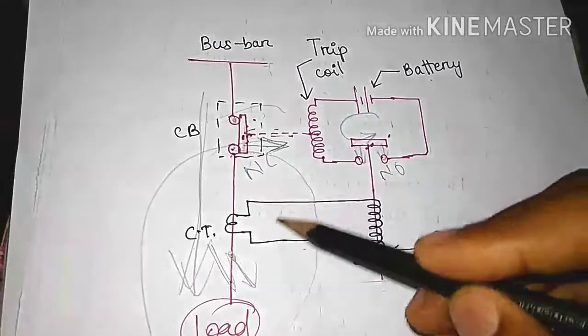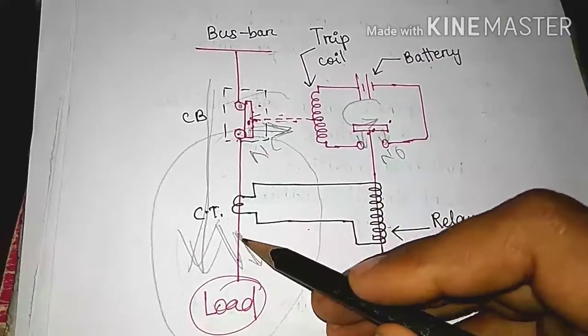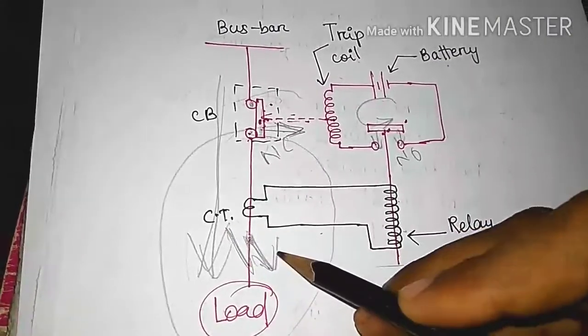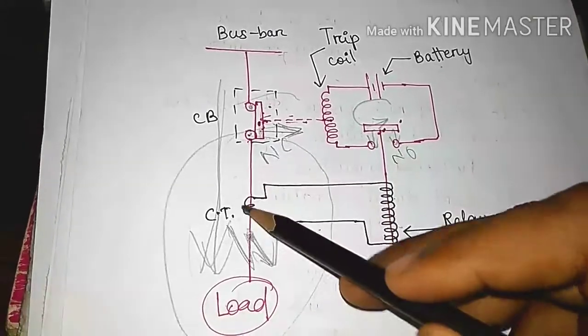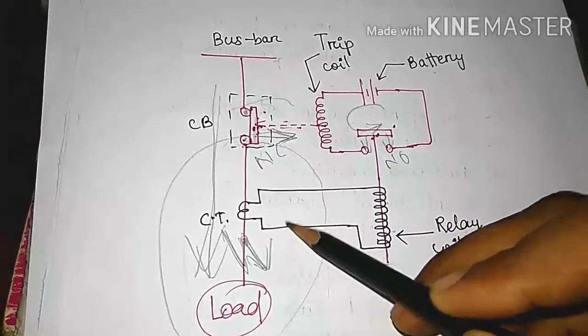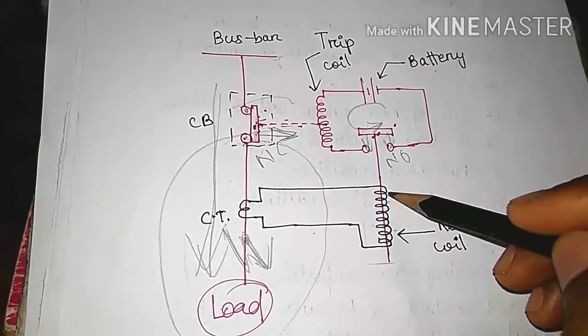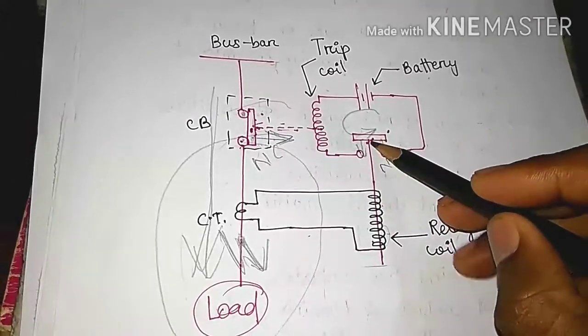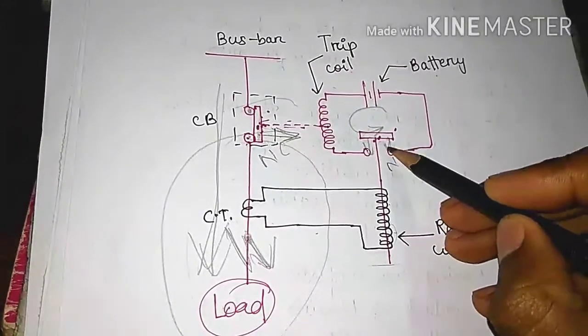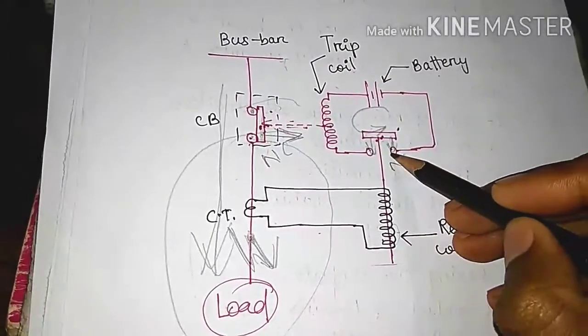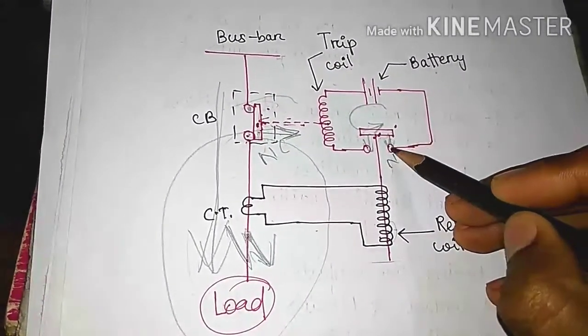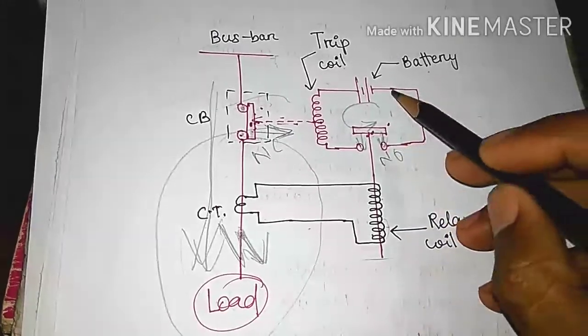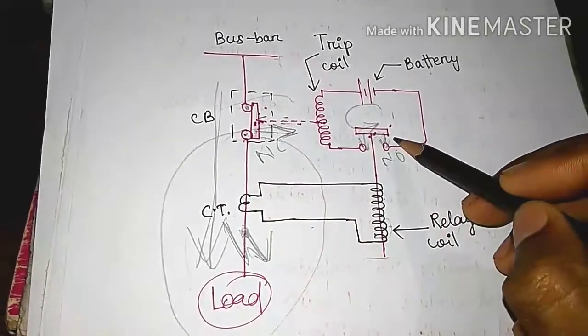But when fault occur in this section, in this point, then maximum current will flowing through the CT or current transformer. In that time, the relay coil will be energized and this moving contact will be magnetized and it will be pulled downward direction. And the moving contact and fixed contact will be bridged or closed to each other. Then this circuit will be completed.